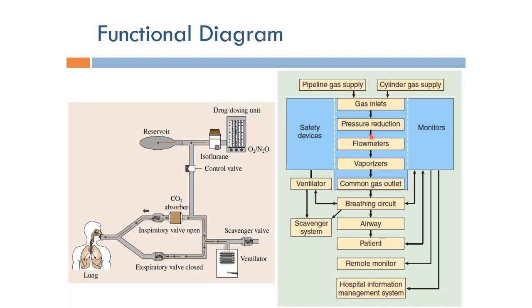And nitrous oxide. These gases go through a pressure reduction stage to ensure that the very high pressures coming from the cylinder or central gas supply are reduced to a safe level for the machine and the patient.